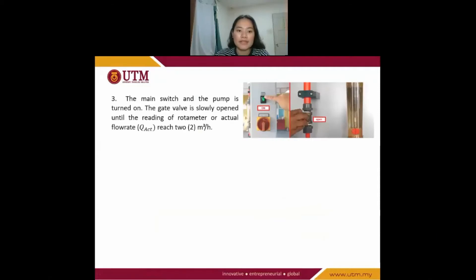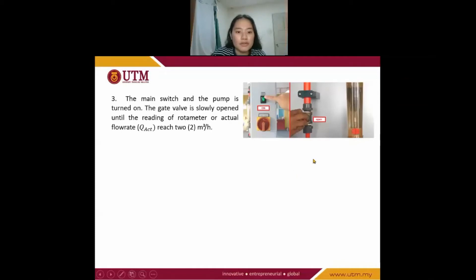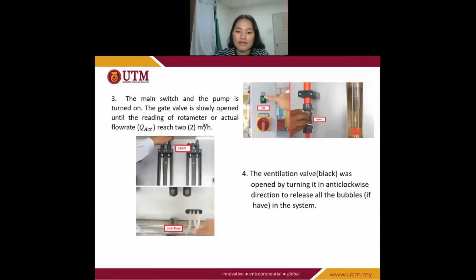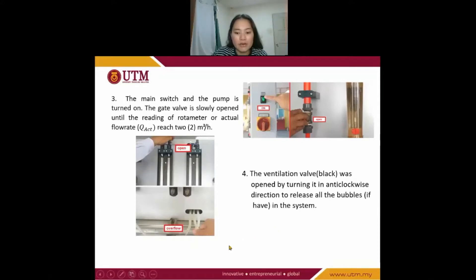Third, the main switch and the pump are turned on. The gate valve is slowly opened until the reading of the flow meter reaches 2 cubic metres per hour. Next, the ventilation valve — the black one — was opened lightly in a counterclockwise direction to release all the bubbles in the system.